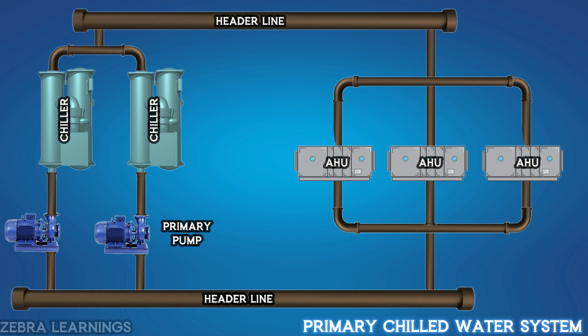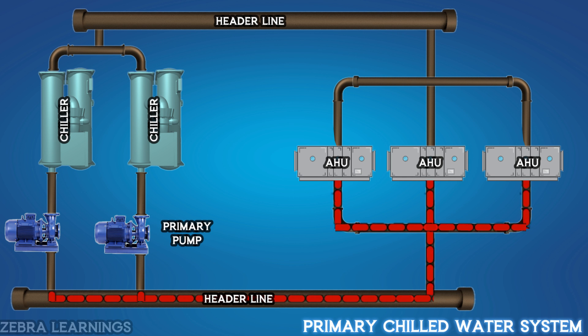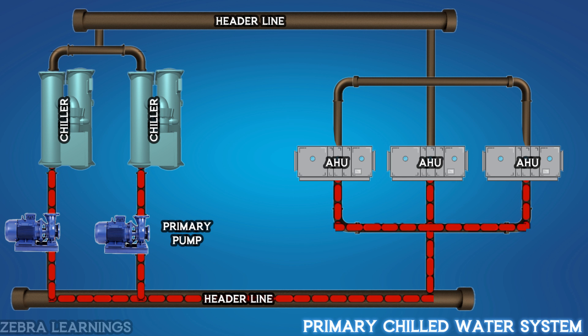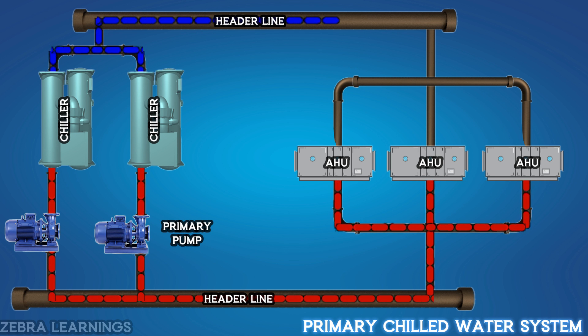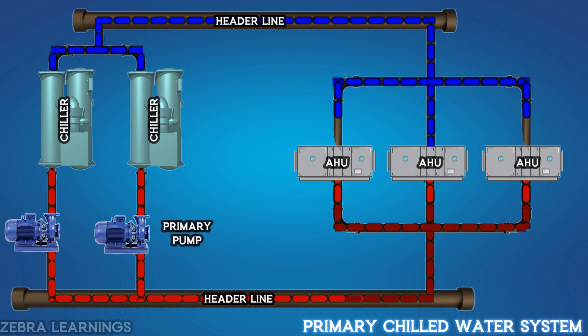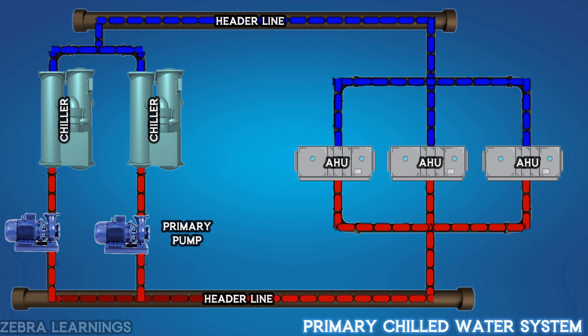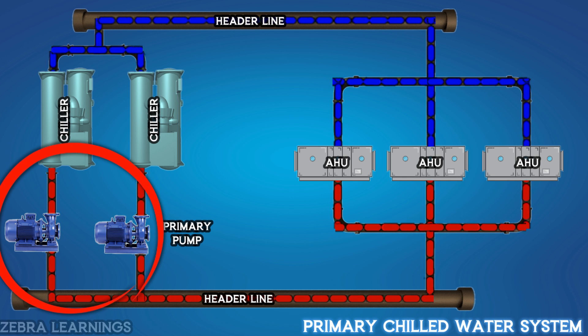Let's discuss the primary chilled water system. The return water from the AHU goes to the return water header line. The primary pump then sucks the water from the header line and sends it to the chiller. The chilled water from the chiller then goes to the supply water header line, and from there it goes to the AHU in the building. The water then returns from the AHU to the chiller via the primary pump. This process continues continuously, and the primary pump is the only pump that does this entire process.